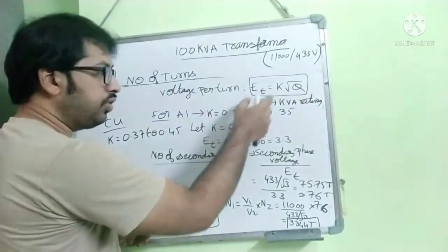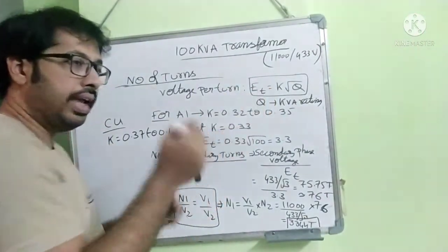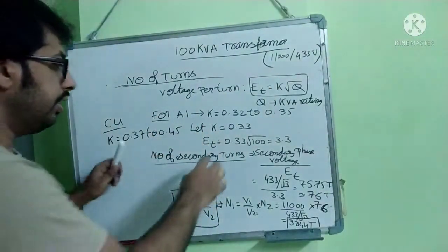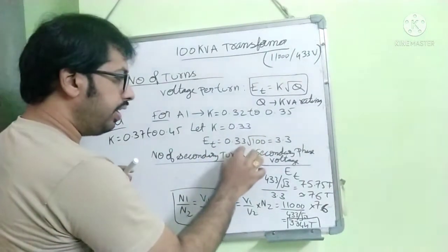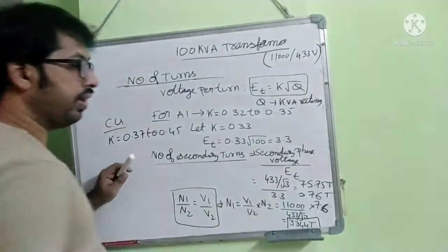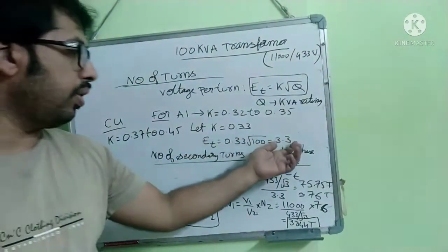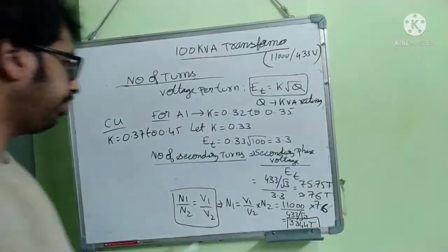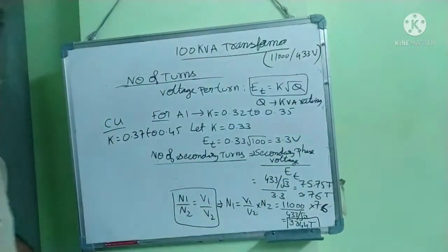Now I am substituting this formula voltage per turn. What is voltage in one turn? That is 0.33 into under root, kVA rating is 100. It is 3.3. Voltage per turn is 3.3 volts.